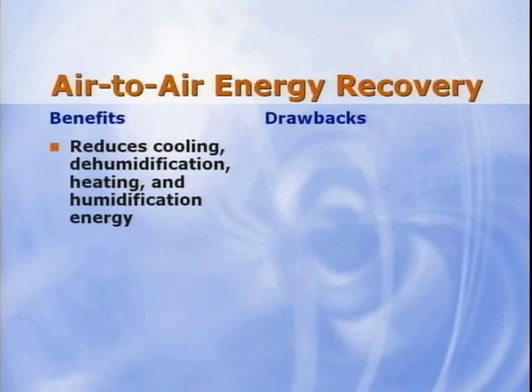A side benefit is that the total energy wheel also transfers moisture from the exhaust air to humidify the dry entering outdoor air. This improves comfort, or it will save energy if humidification equipment is being used. Using air-to-air energy recovery offers the following benefits. It reduces cooling and dehumidification energy, and also reduces heating and possibly humidification energy.